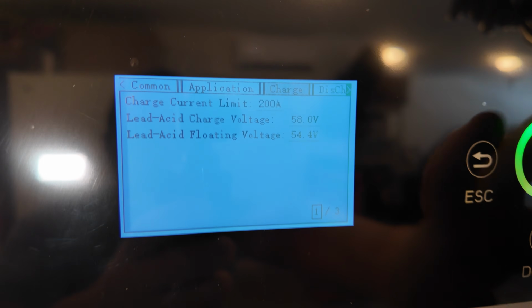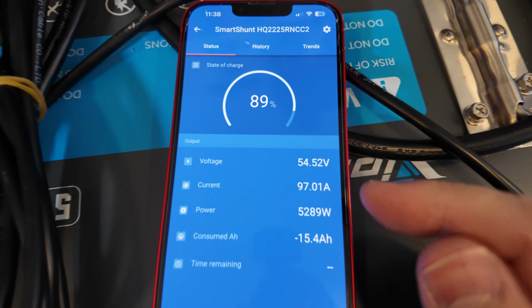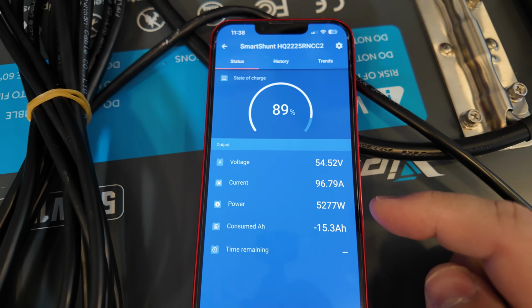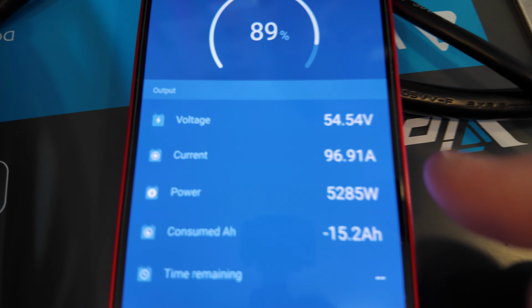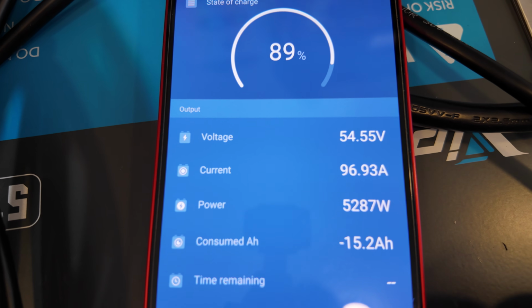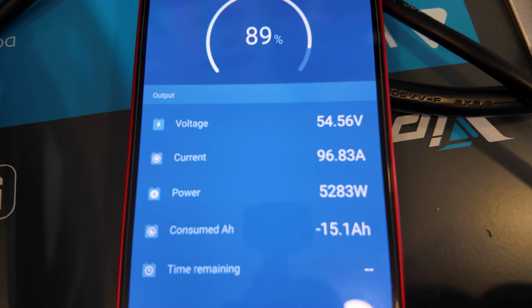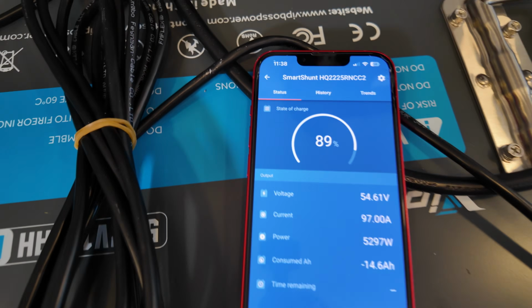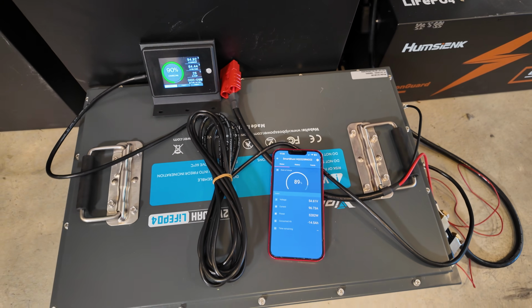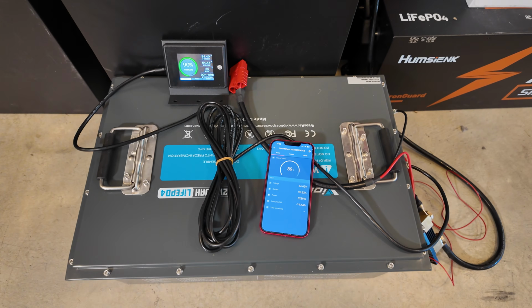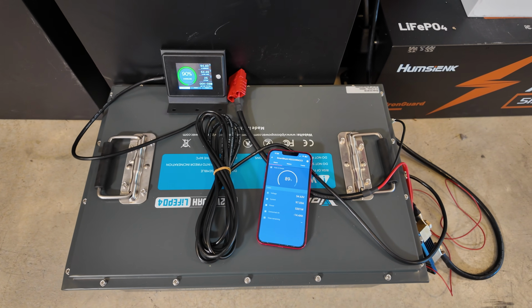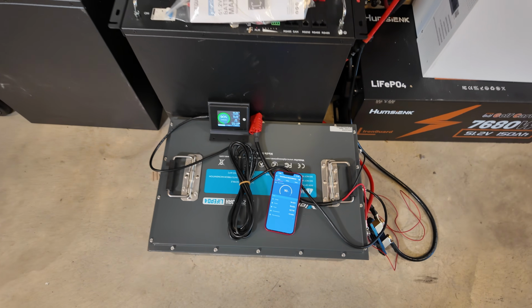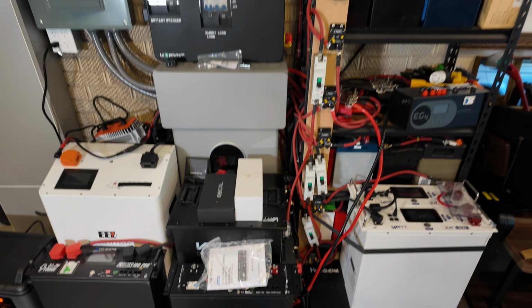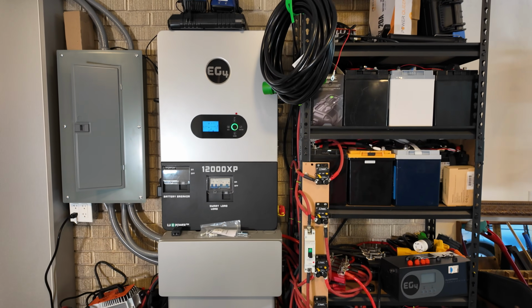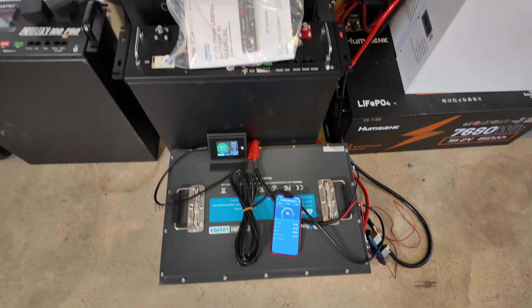So I do have this set to 200, but it looks like the battery is going to limit its charging to 100 amps, which isn't a bad thing, because we're putting in about 96, even though I'm programmed to be at a full 200. So I'm sorry, I don't have the capability to pull a full 200 amps from this, but it's at least solid at 100 amps, which for most of us building a whole home power backup like this, 100 amps is very typical.